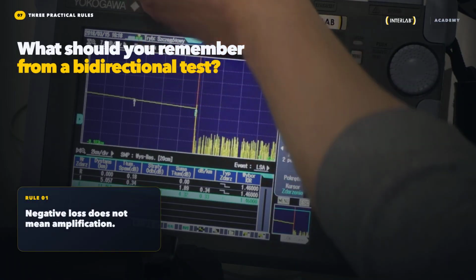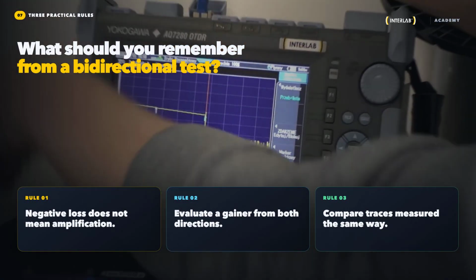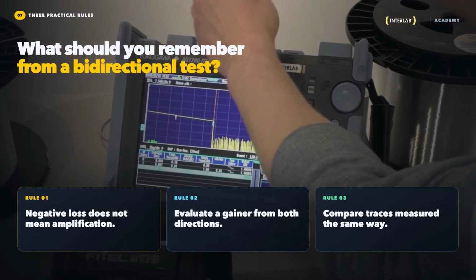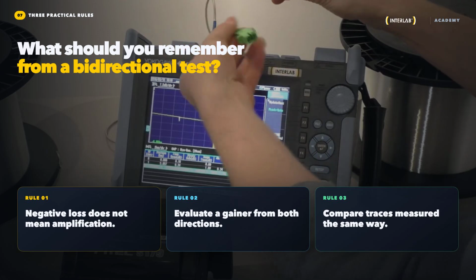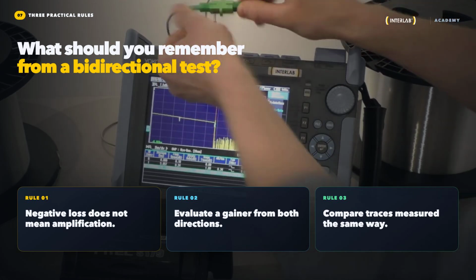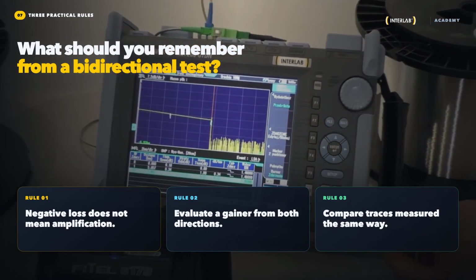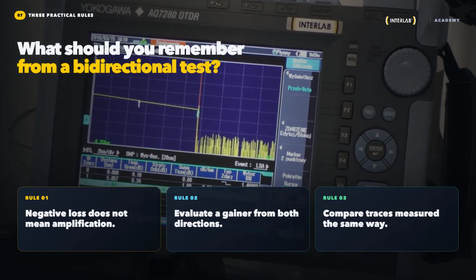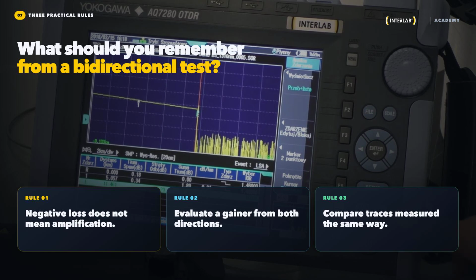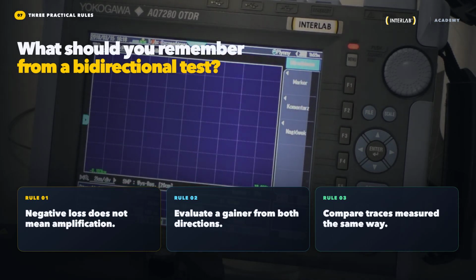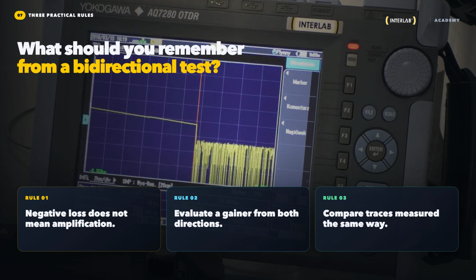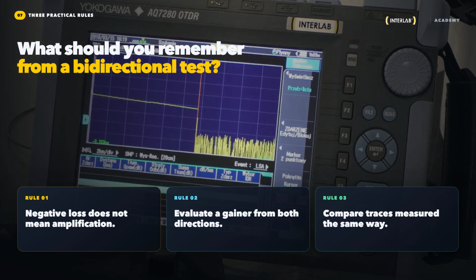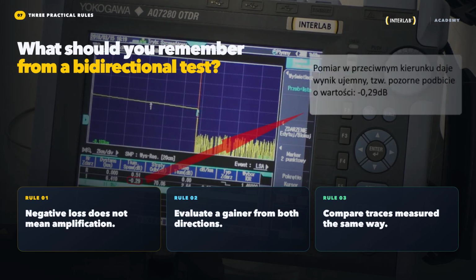Three practical rules come out of this test. First, a negative event loss does not mean that the splice is amplifying light. It points to a backscatter mismatch between the fibers. Second, to evaluate a gainer properly, test the splice from both directions and average the two results. Third, both traces need matching settings and clean sections of trace around the event. Average comparable results, not two random readings. A one-way trace is still excellent for locating an event. It is not always enough to evaluate its loss accurately.